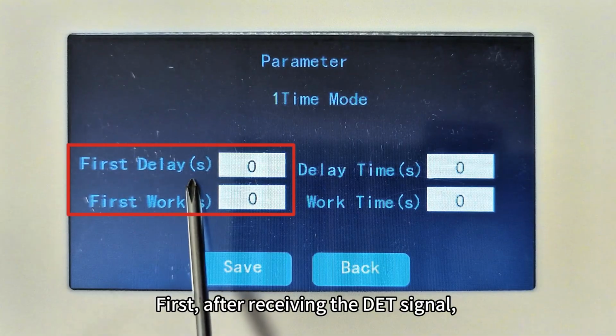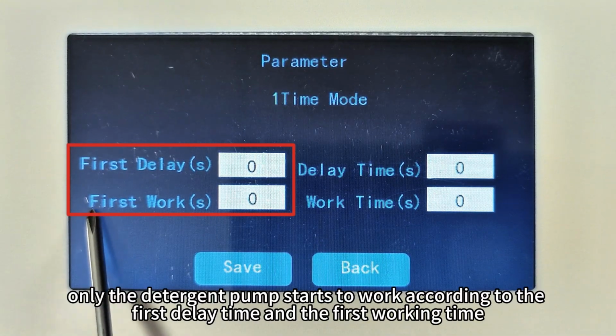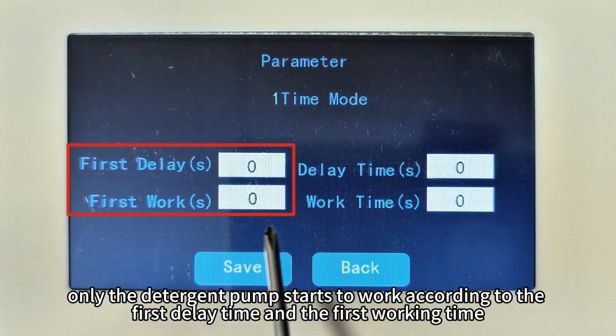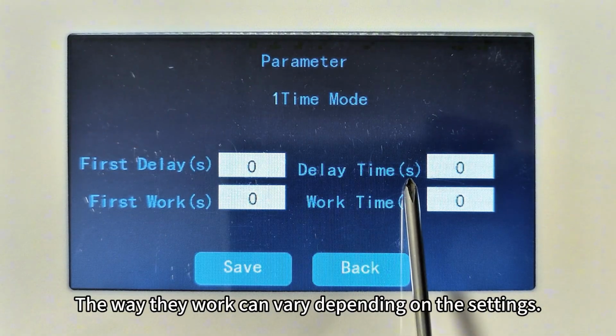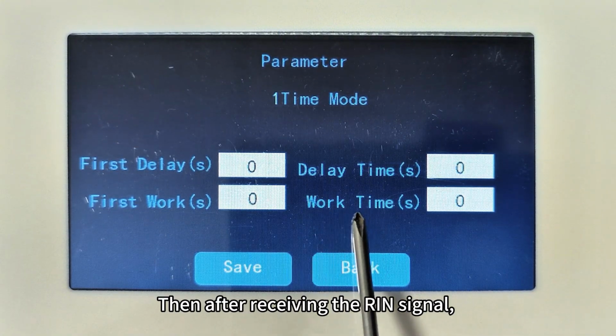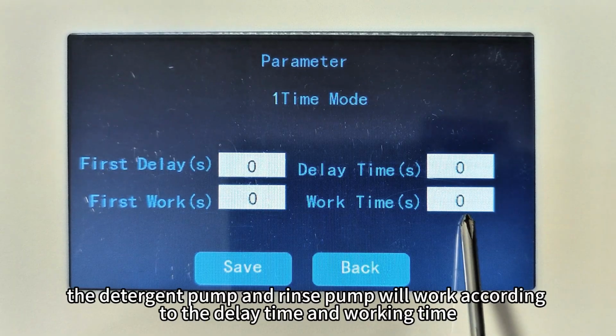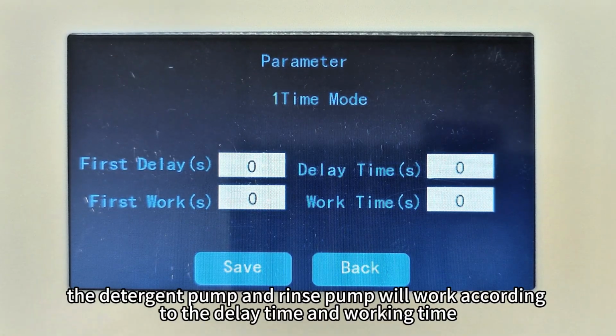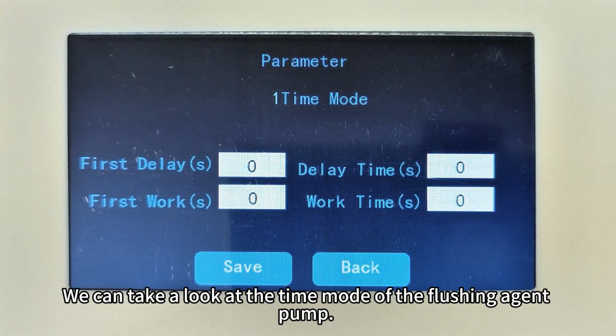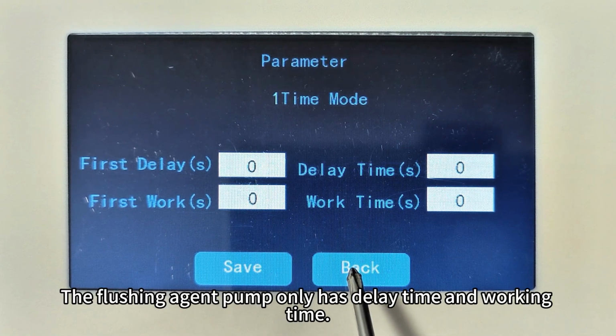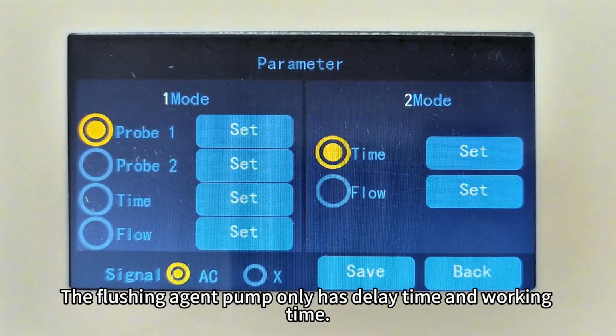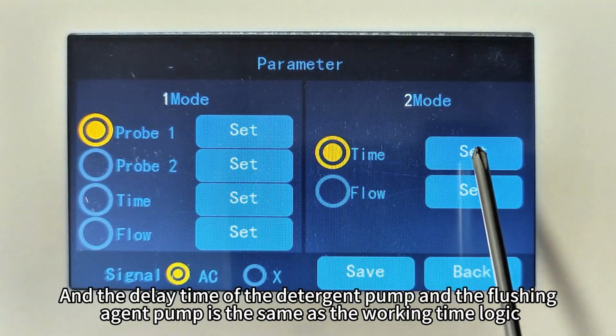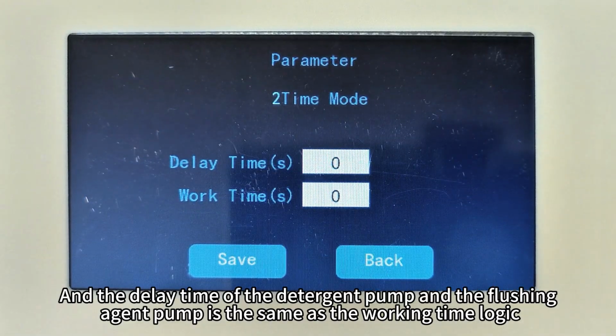First, after receiving the DET signal, only the detergent pump starts to work according to the first delay time and the first working time. The way they work can vary depending on the settings. Then after receiving the RIN signal, the detergent pump and rinse pump will work according to the delay time and working time. We can take a look at the time mode of the flushing agent pump. The flushing agent pump only has delay time and working time, and the delay time of the detergent pump and the flushing agent pump is the same as the working time logic.